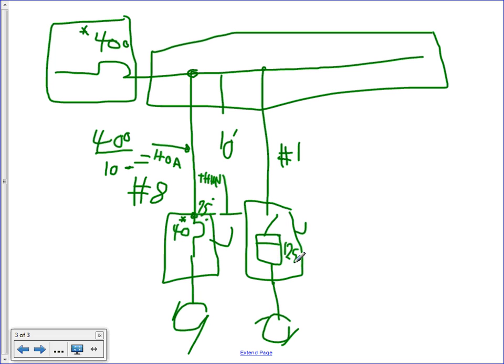That machine, you guys were sizing with my friend Jeff Keljic here yesterday. So you can see what size, the overcurrent device of that machine cannot be more than 125. That's the only condition that you have. As long as you can meet that condition, the tap rule is good to go. Any comments, guys, about the 10-foot rule?